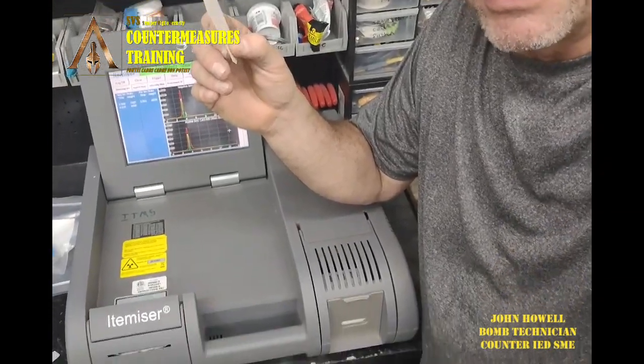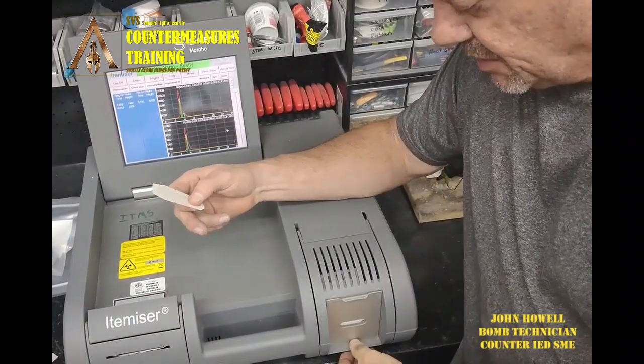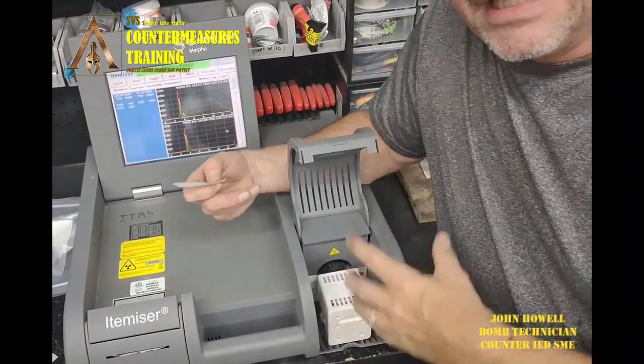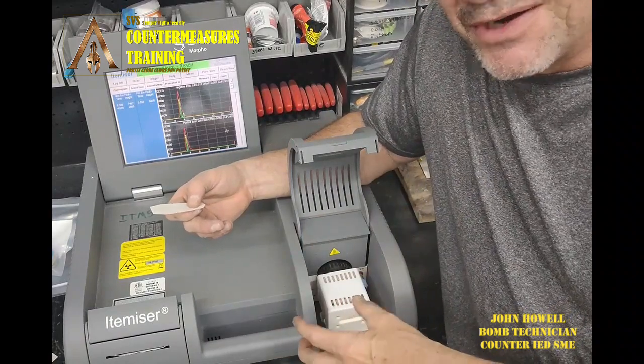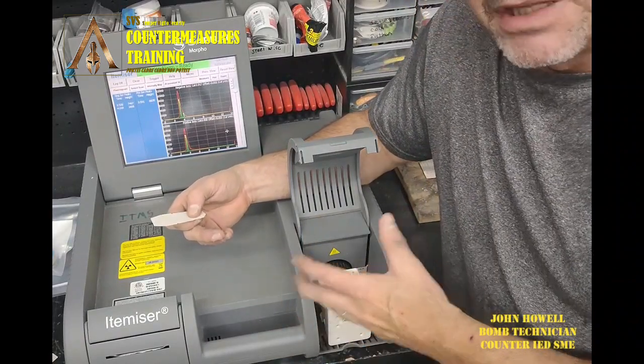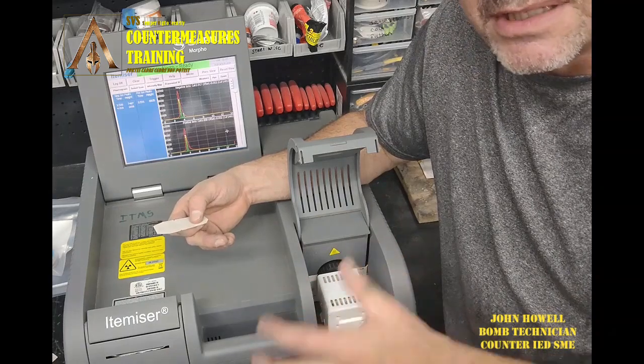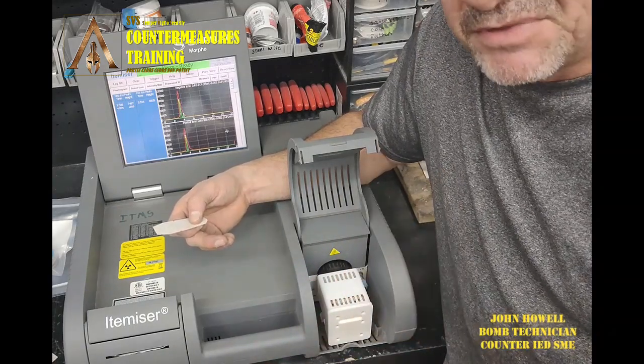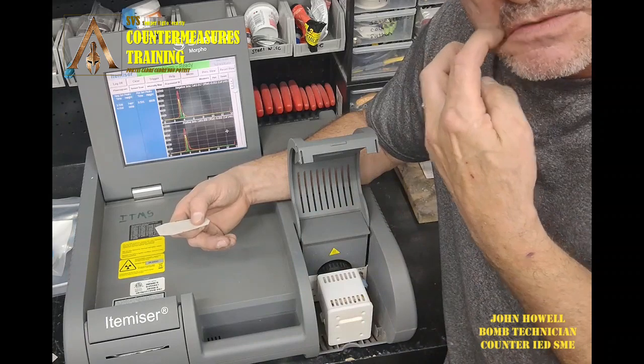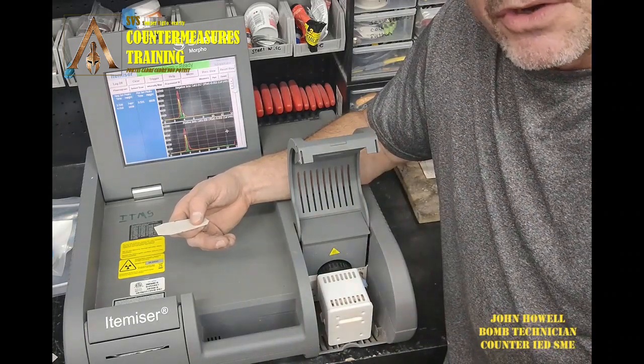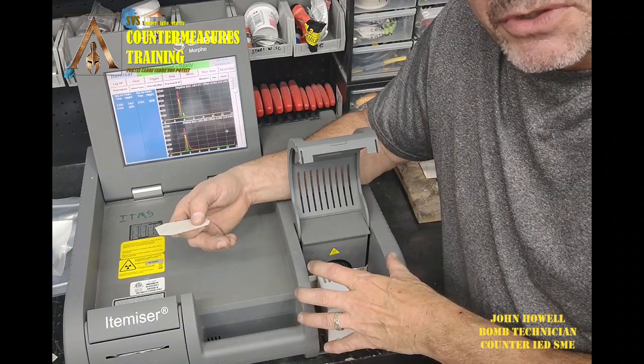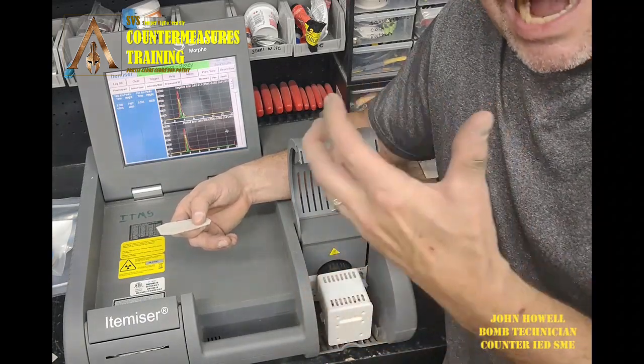Now the desorber, again, is on this system. It's located right here, right underneath here, and it is literally a toaster, all right? And this one right now is probably, I believe, heated up to around 220 degrees Celsius, which is the optimum temperature for detecting explosives. Now, if I switch this over to narcotics, it's going to raise the temperature of the desorber to a higher level.